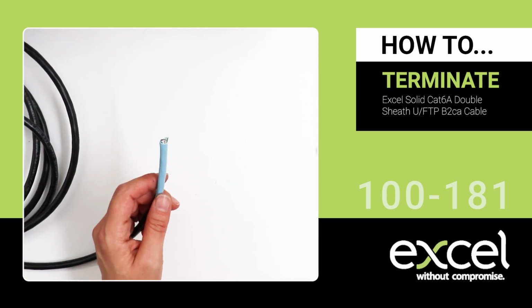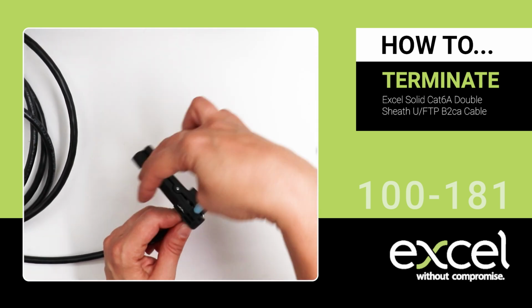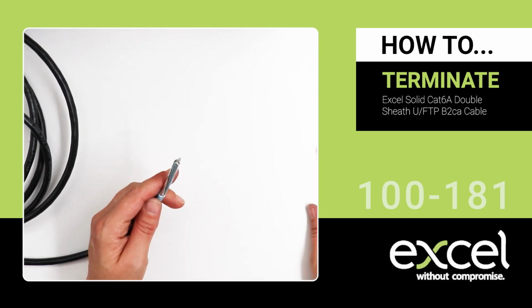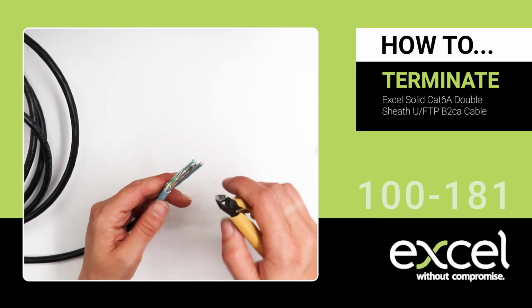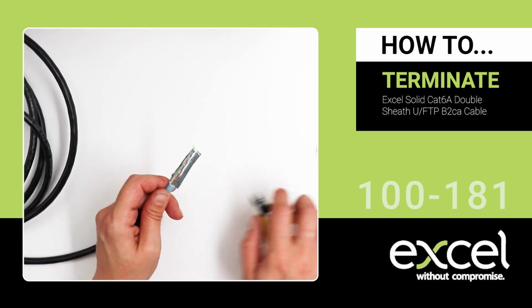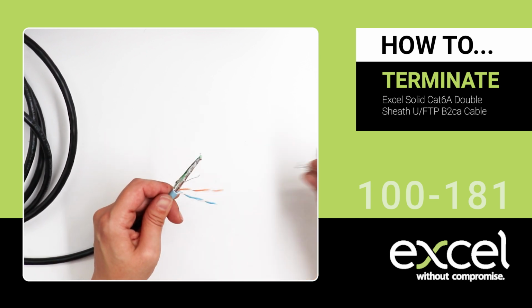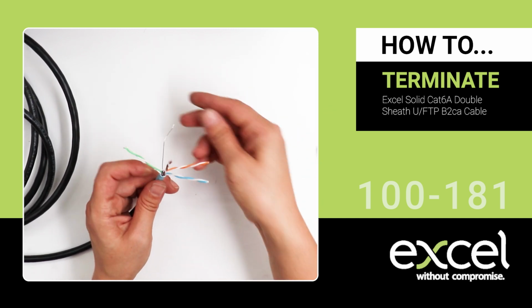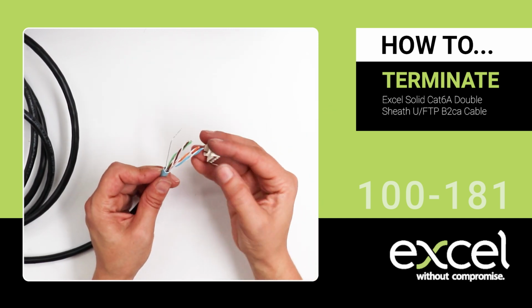Strip about 40 mm off the cable's B2ca jacket using the peg-style cable stripper. Score the sheath, bend the cable to break it, and remove the jacket. Snip and remove the foil from the pairs with the side cutters. Be careful not to cut the drain wire. Unwrap the foil and remove from the individual pairs of cable.